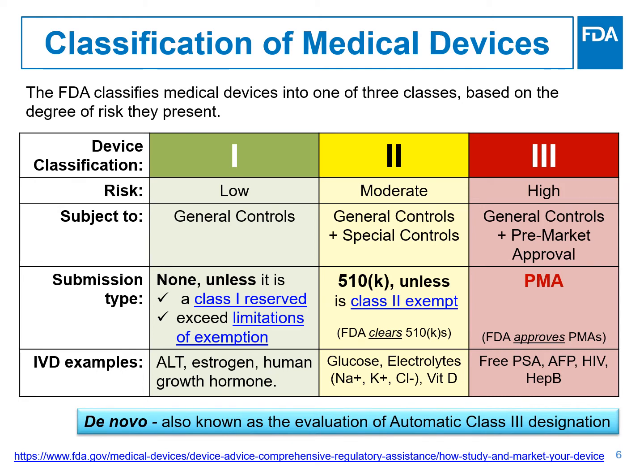Devices that were not known before the date of the Medical Device Amendments of 1976 have not been classified by FDA and are automatically classified into Class 3 regardless of the level of risk for that product. However, in 1997, the de novo path was established and enacted. This is a classification process that uses a risk-based strategy that provides a means to classify novel device types into Class 1 or Class 2. If the de novo is granted, it establishes a new device type.